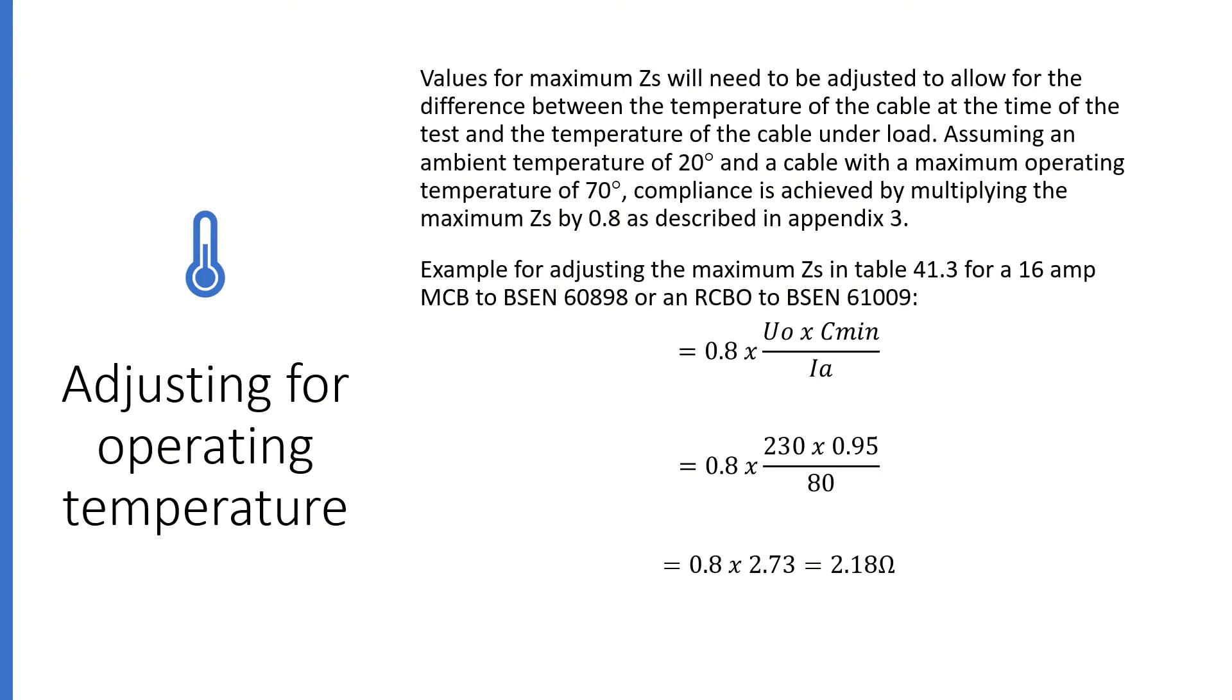So in other words, the values for maximum Zs will need to be adjusted to allow for the difference between the temperature of the cable at the time of the test and the temperature of the cable under load. So assuming an ambient temperature of 20 degrees C and a cable with a maximum operating temperature of 70 degrees C, compliance is achieved by multiplying the maximum Zs in table 41 by 0.8, as described in Appendix 3 of BS7671.